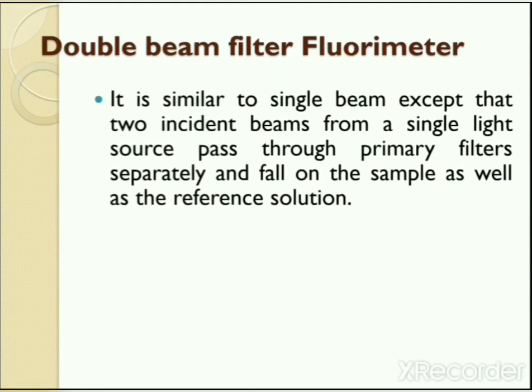Next is the double beam filter fluorimeter. In this type of instrument, two incident beams from a single light source pass through a primary filter separately and fall on the sample as well as the reference solution. The advantage of this type of instrument is that it can measure the sample as well as the reference at the same time. This reduces the chances of errors produced by changes in the intensity of radiation when sample and reference are analyzed separately, as in single beam instruments.